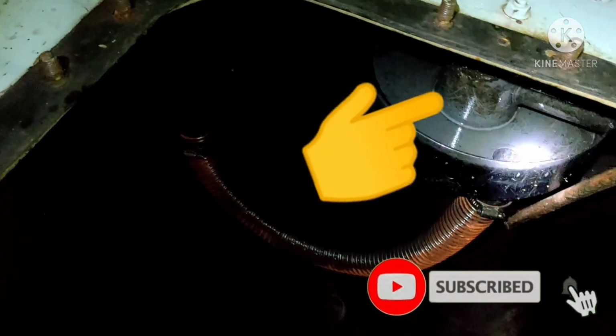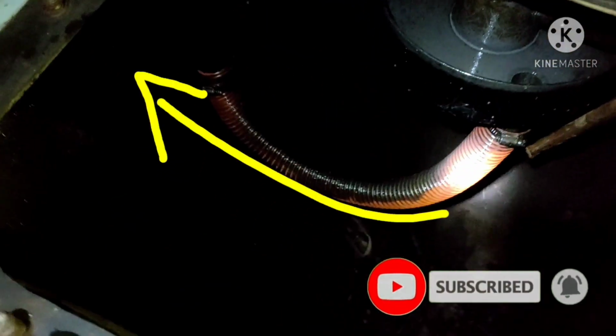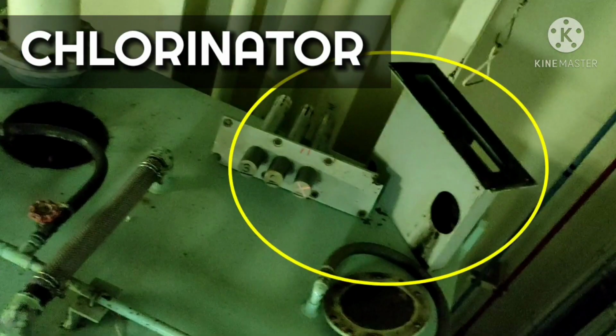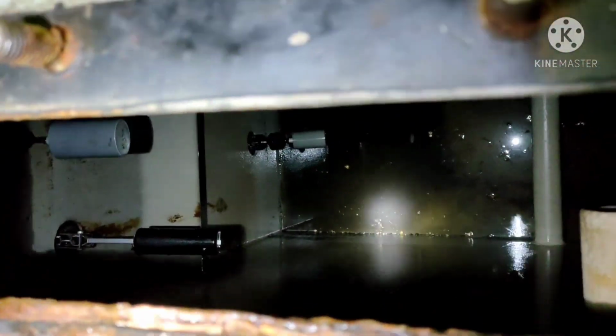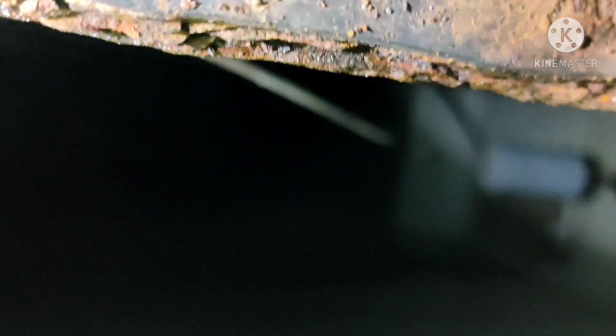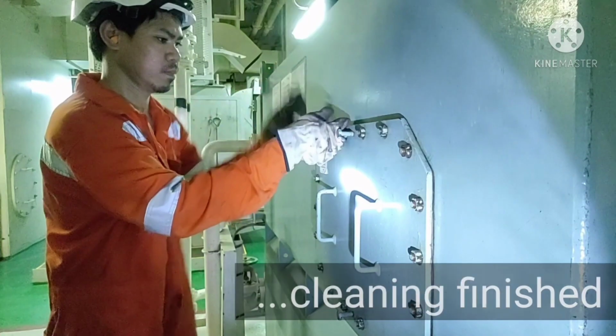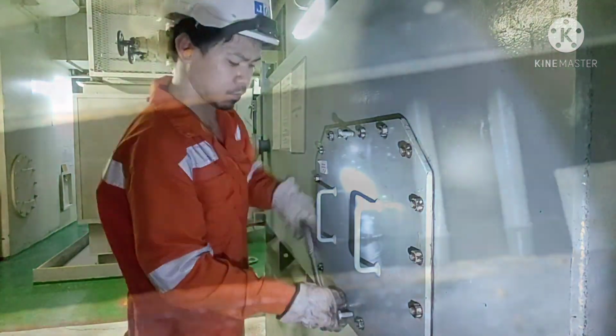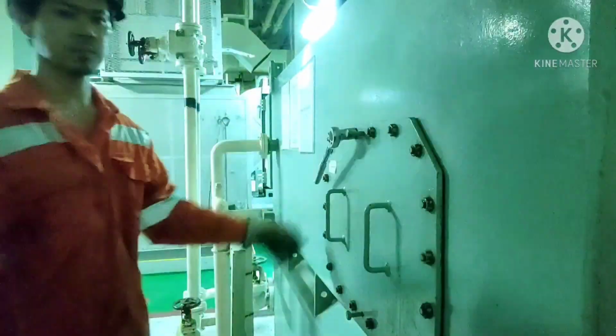During normal operation, solid particles are suctioned on this plate and sent back to the aeration chamber, while pure liquids overflow to the chlorinator and are collected in this tank called the chlorination chamber. Now that all tanks are clean and inspected, let's test the high-level alarm by lifting this float switch. Cleaning finished, we can now close all manholes and fill up with water.